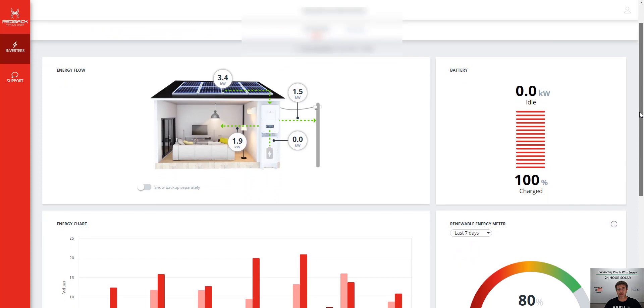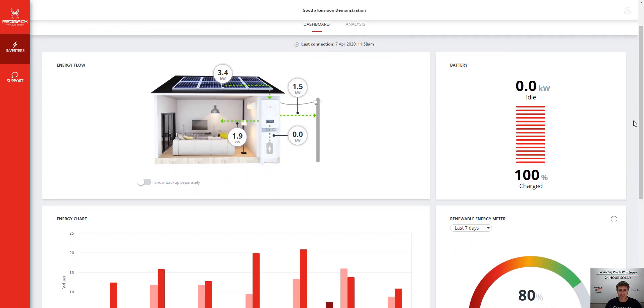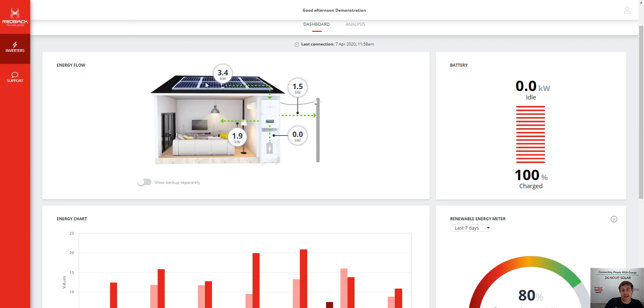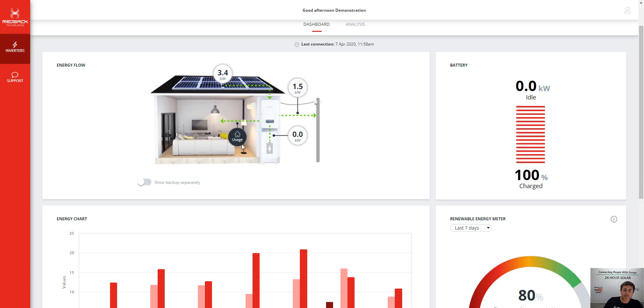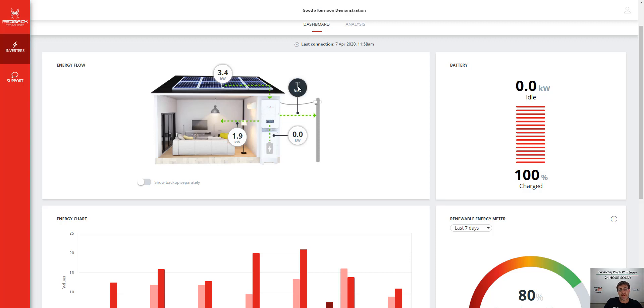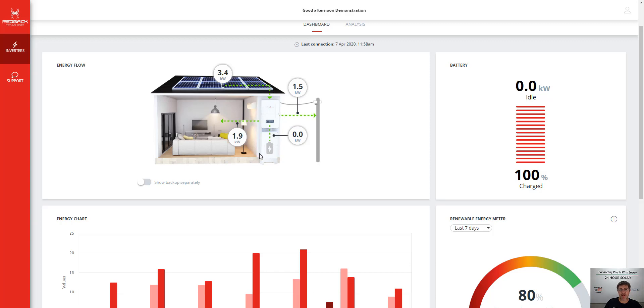I love this Redback app, it's actually one of my favorites in the systems that we monitor and install. So this is basically what's going on, it's just really simple. Right now it's saying that the solar panels in this system are on 3.4 kilowatts, and it's coming down 1.9 kilowatts going to the house, just hover over the tab to tell you what's going on, and 1.5 kilowatts going back to the grid right now, and nothing is coming from battery. So it's a really great interface.